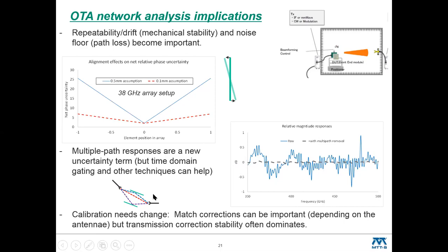Fortunately, they do have different time delays, so there might be some amelioration methods available. Indeed, there are classical VNA time domain techniques where you transform into the time domain, isolate out the part you care about, throw away the rest, and then transform back to the frequency domain. That's really what's shown here in gray. You can take care of a fair number of problems, assuming these multipaths are sufficiently different in distance and you have enough sweep range to get enough resolution, since resolution goes as one over the sweep range. A narrow band device presents a bit more of a challenge there.